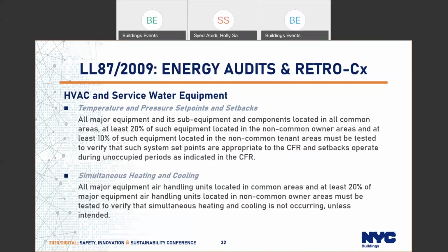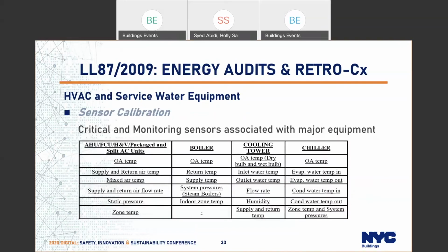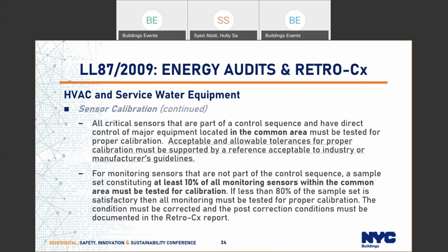The rule amendment also clarifies on the temperature and pressure set points and setbacks, simultaneous heating and cooling for all major equipment, air handling units. It prescriptively lists all critical and monitoring sensors that are associated with major equipment and clarifies on the scope of work for Local Law 87. All critical sensors that are part of a control sequence and have direct control of major equipment located in the common area must be tested for proper calibration. There is a different sampling requirement for monitoring sensors.